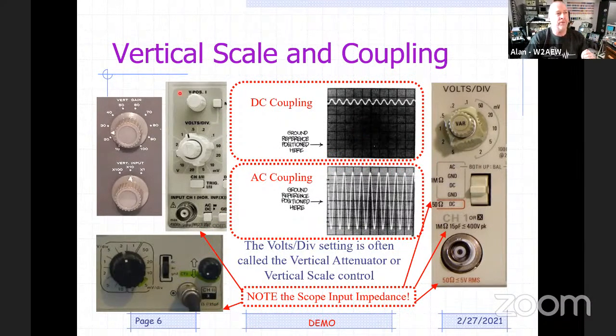Eventually you'll run out of vertical position adjustment. So what AC coupling allows you to do is throw a series capacitor in that input path, get rid of the DC component, and then you can adjust the volts per division however you want. Now you're just focusing on the AC wiggle, the ripple on top of the power supply. It's funny that often if you're looking at DC signals to find ripple, you'll use AC coupling — a bit counterintuitive, but that's really what you'd often do.